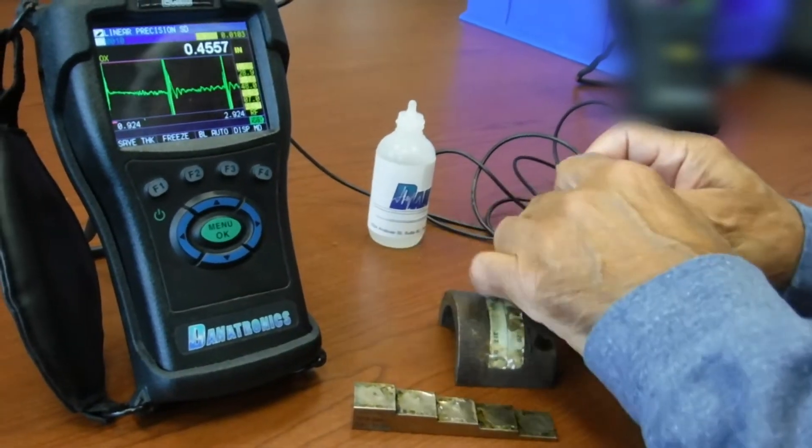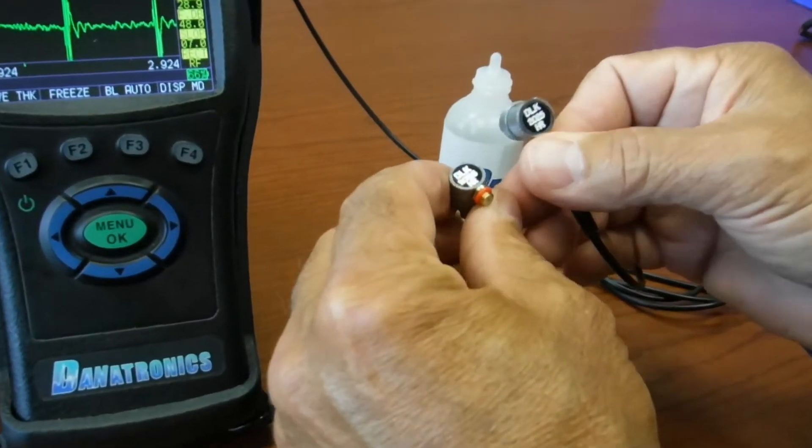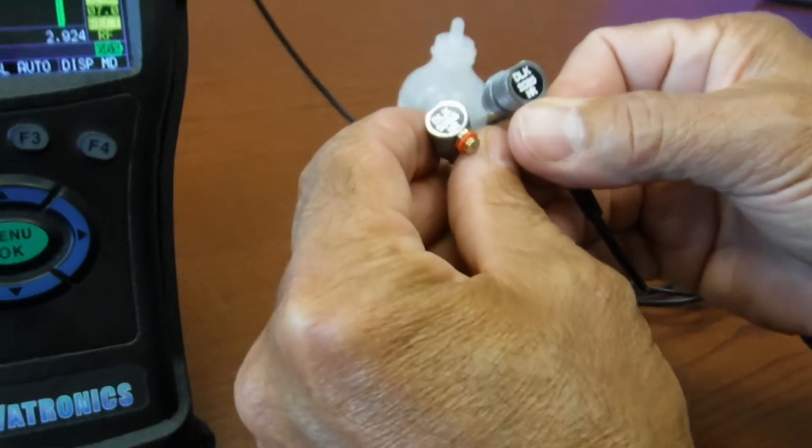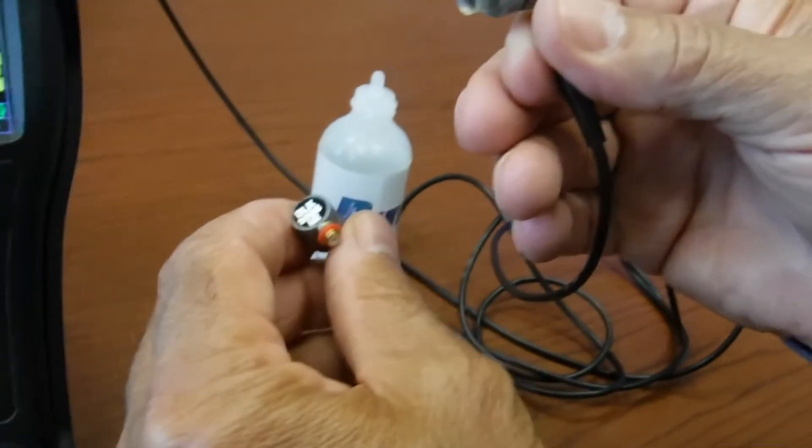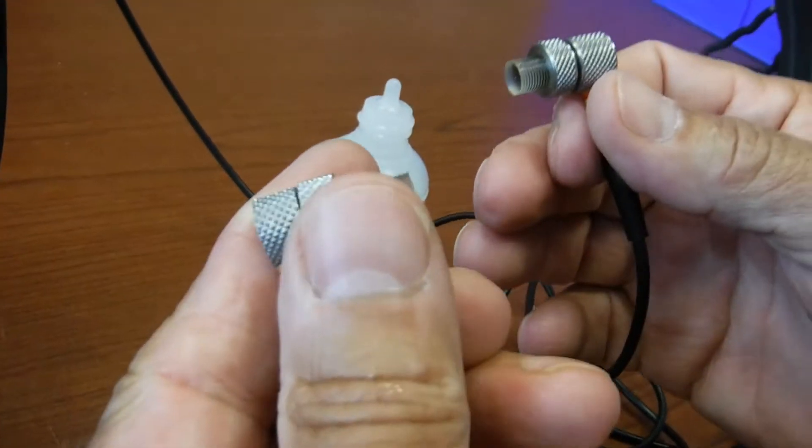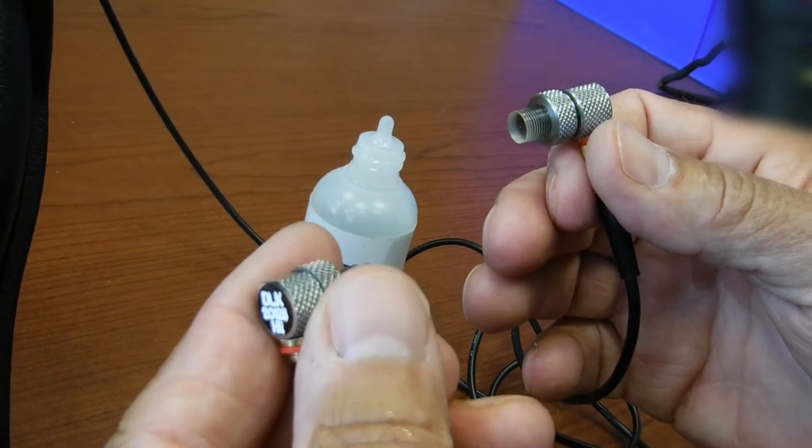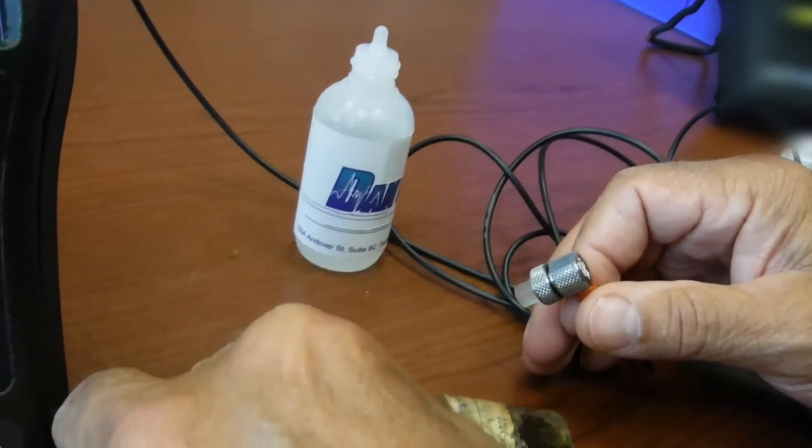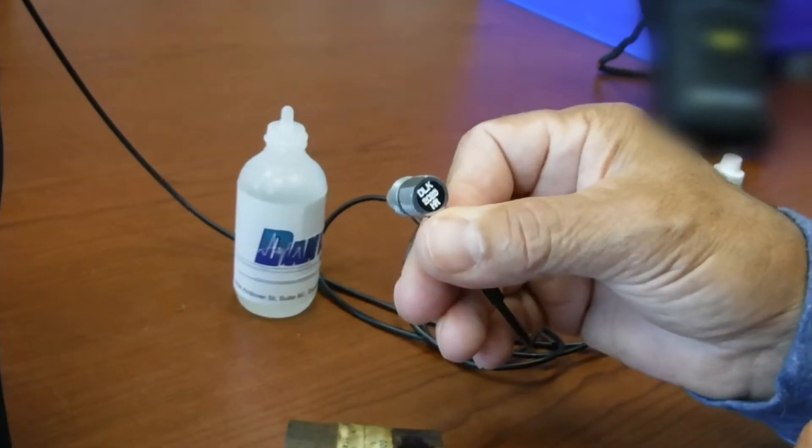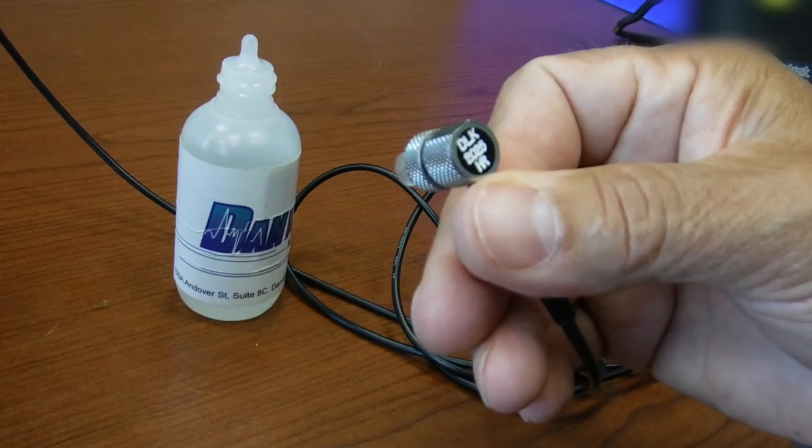There's two transducers that are available, both 20 megahertz longitudinal delay lines. One's a 20 megahertz quarter inch element. The other is a 20 megahertz eighth inch element. These are simply chosen based on tube diameter, pitting and whatnot. I'm going to be using the quarter inch element for the sake of today's demonstration.